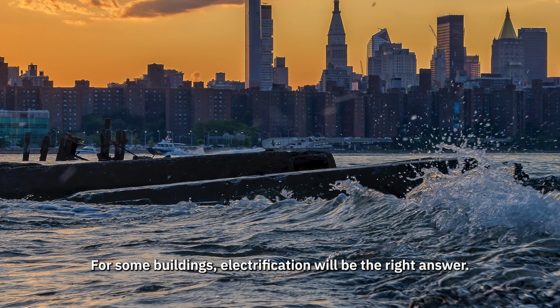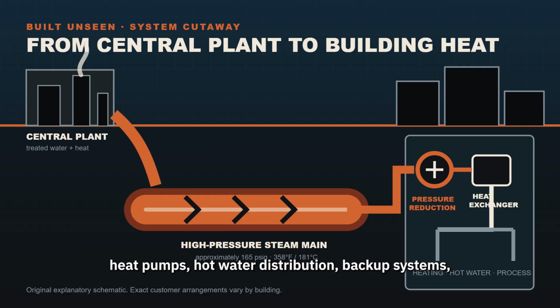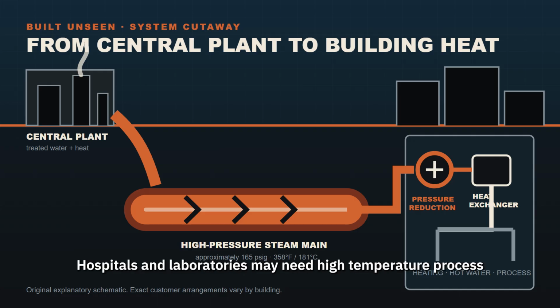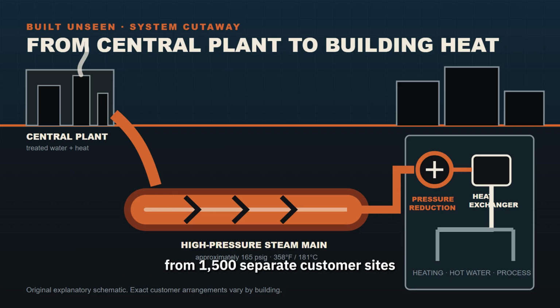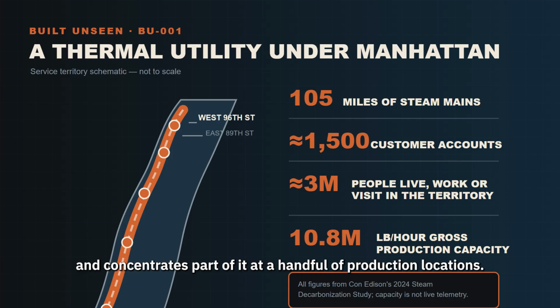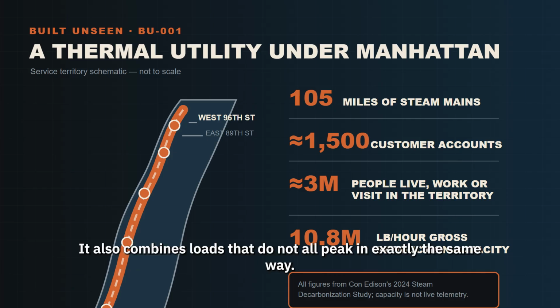For some buildings, electrification will be the right answer. But Manhattan is not a blank construction site. Large existing buildings can require new electrical service, heat pumps, hot water distribution, backup systems, and major interior work. Mechanical equipment needs physical space. Hospitals and laboratories may need high-temperature process steam that ordinary space heating heat pumps do not provide. The district network moves that complexity away from 1,500 separate customer sites and concentrates part of it at a handful of production locations. It also combines loads that do not all peak in exactly the same way.